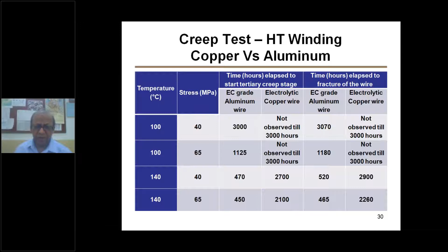You can also see the results tabulated over here. When temperature is 100 degrees centigrade, which is the normal temperature in distribution transformers, stress should be 40 megapascals, and then EC grade aluminum wire reaches the tertiary state after 3000 hours, which is not happening in the case of copper. So you can think that the creep behavior of aluminum is much higher, maybe 6 to 20 times depending on the various temperature levels and pressure. Therefore, very high creep in the case of aluminum.